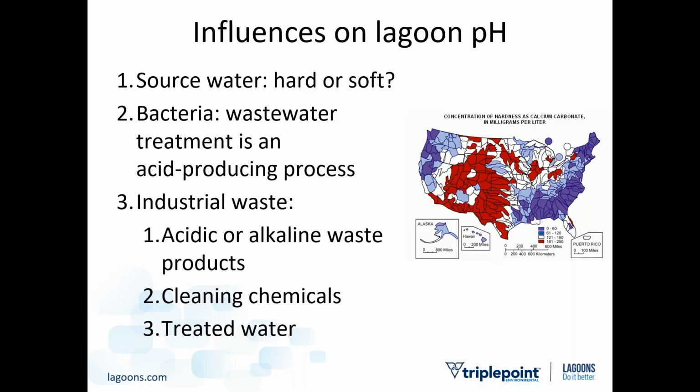And then the second thing, now that it becomes wastewater, it gets all these contaminants in it. Usually those contaminants end up fairly neutral. Nobody is using so much cleaning solution in their house, dumping vinegar down the drain to make it acidic, to really offset the fact that human waste is fairly neutral. There's a lot of neutralizing effect of the source water itself. So a lot of the time, your water coming down the pipe is maybe a little bit higher than neutral, 6.8 to the mid 7s, but it's pretty close.